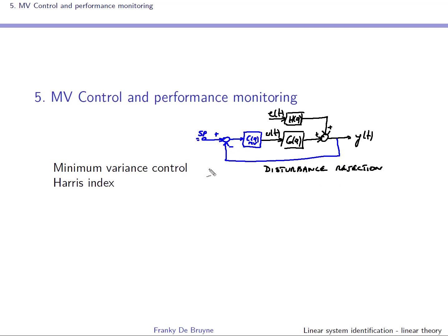This minimum variance controller, when you consider linear controllers, will be the one that is optimal in disturbance rejection, in the sense that the variance of Y will be as small as possible. So the idea will now be to do performance monitoring — a really interesting field. It uses data from the closed-loop system to monitor control performance. Most of the time, people think control performance monitoring is about tracking, so following a setpoint.